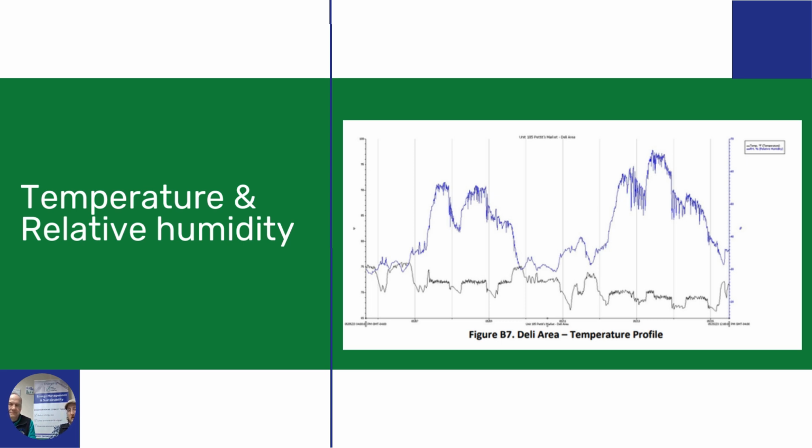But these could give us some data points that help make a decision, or again, ask the question, hey, is there something going on with the way the building envelope is controlled, the dock doors, the way the windows either operate or don't operate, or the outside air or makeup air unit. Just had an interesting conversation earlier today about a continuing trend in seeing the outside air equipment in buildings that isn't functioning correctly.